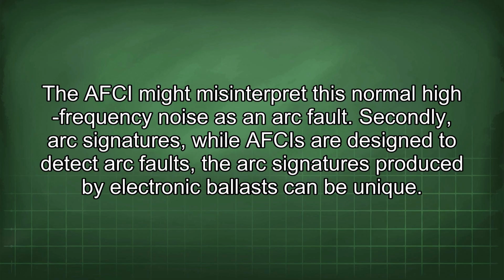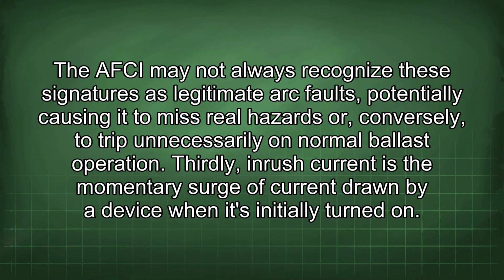Secondly, arc signatures. While AFCIs are designed to detect arc faults, the arc signatures produced by electronic ballasts can be unique. The AFCI may not always recognize these signatures as legitimate arc faults, potentially causing it to miss real hazards or, conversely, to trip unnecessarily on normal ballast operation.